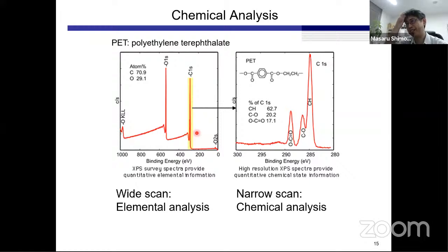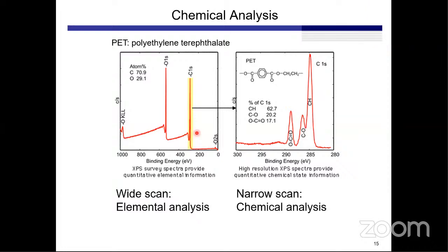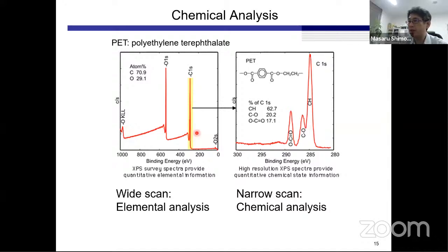Difficult question. In the case of a very flat film, XPS is used very effectively for quantitative analysis. But in the case of very corrugated systems, quantitative information is sometimes very difficult. But my recommendation is, if available, you can use two different energy excitation sources, like aluminum K-alpha and magnesium K-alpha. In the case of my XPS, we have a silver target that has a very high energy. So if we use different types of energy excitation, we can control the kinetic energy range.